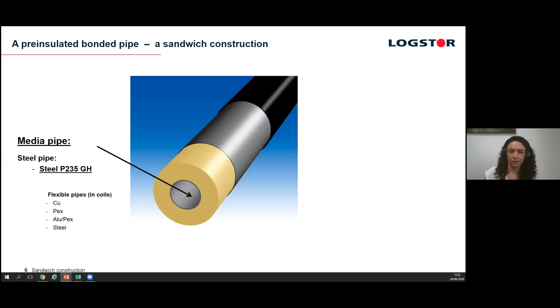Then we have insulation. Typically in a district heating pipe we'd have polyurethane, PUR, which goes up to a maximum of 120 degrees, or a peak of 140 for up to 300 hours a year. If you want to get into district heating at higher temperatures, or towards the steam end of the market, we do PIR foam, which handles up to 170 degrees. We also have the diffusion barrier, which is basically an aluminium foil that prevents gases diffusing, but I'll talk about that in more detail later.